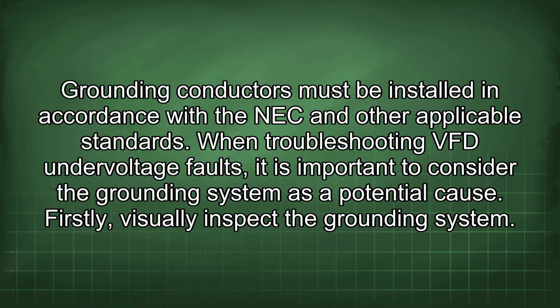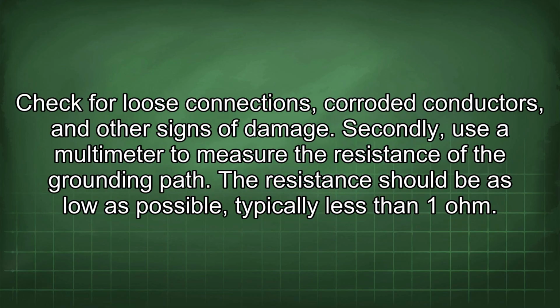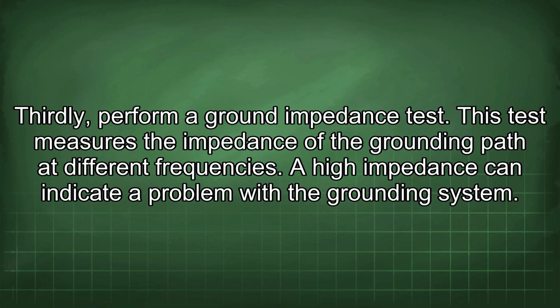When troubleshooting VFD undervoltage faults, it is important to consider the grounding system as a potential cause. Firstly, visually inspect the grounding system. Check for loose connections, corroded conductors, and other signs of damage. Secondly, use a multimeter to measure the resistance of the grounding path. The resistance should be as low as possible, typically less than 1 ohm. Thirdly, perform a ground impedance test. This test measures the impedance of the grounding path at different frequencies. A high impedance can indicate a problem with the grounding system.